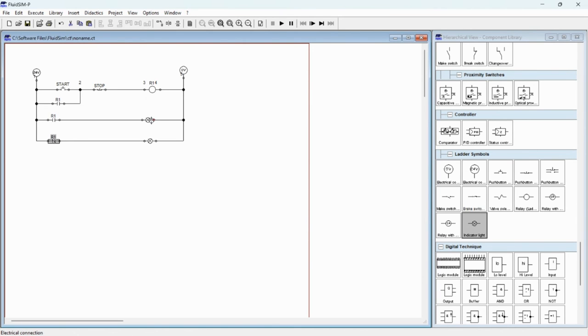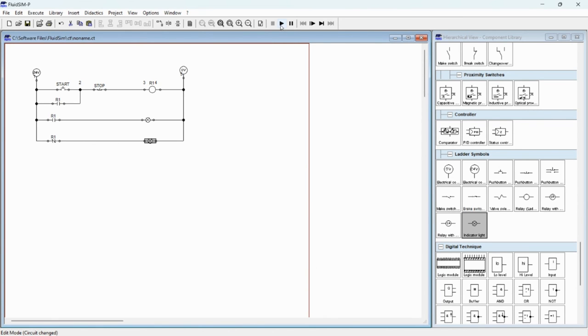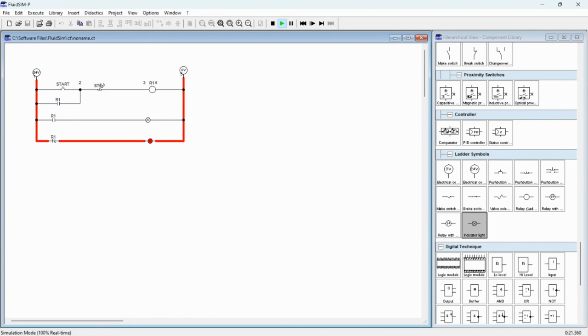Now the circuit is ready. When you press the start button, the relay turns on and the green light will light up. When you press the stop button, the relay will stop and the power flows through the normally closed contact and the red indicator will turn on. Let's check — press the play button. Currently the relay is not on, so the power flows through the relay normally closed contact and the red indicator is lit up. If you press the start button, the relay turns on, power flows through the relay, and the green light turns on. When you press stop, the relay turns off, power flows through the normally closed contact, and the red indicator turns on.